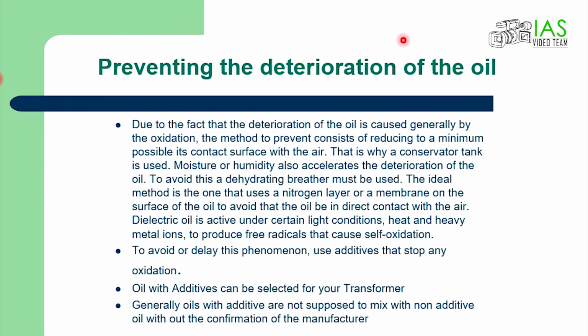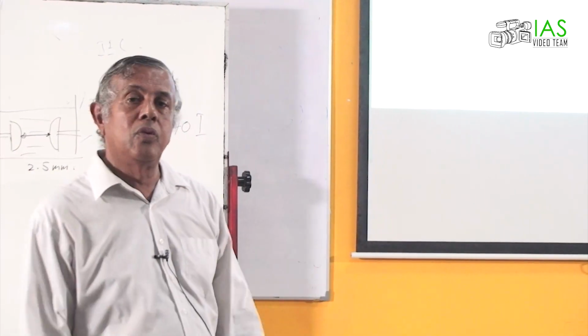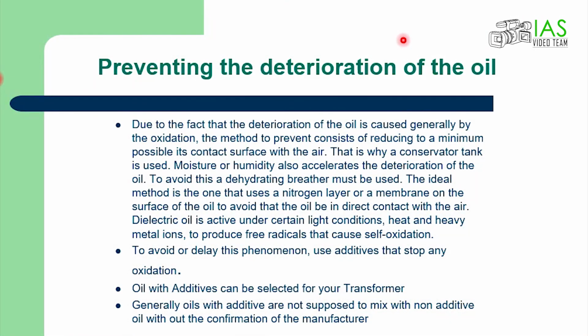Preventing the deterioration of the oil: deterioration of oil is caused generally by oxidation. The method to prevent it consists of reducing its contact surface with air to the minimum possible, by a silica gel breather and so on. And sometimes a nitrogen layer is used to do that. To delay this phenomenon, use additives. You put additives to delay the oxidation. Oil with additives can be selected for your transformers.